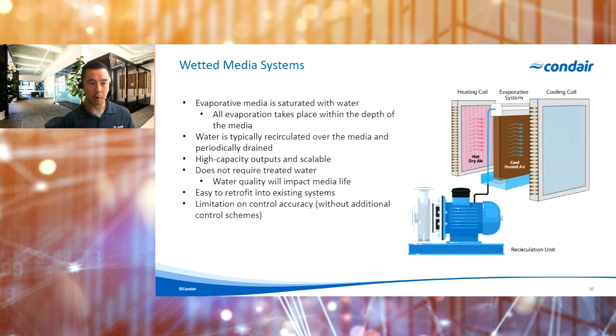Now, if we're using mains water, potable water, or well water, or any water that has minerals in it, as that water is evaporated off of the media, those minerals, whatever is in there, will start to concentrate up, and over time, we will potentially start to see a scale form on the surface of the media. So with most systems, as a means to control or help reduce that mineral buildup, the systems will typically perform a blowdown cycle, drain some water out, bring in some fresh makeup water in order to maintain media life, as well as optimize the water usage as well. And there's a few different ways that water quality can be controlled.